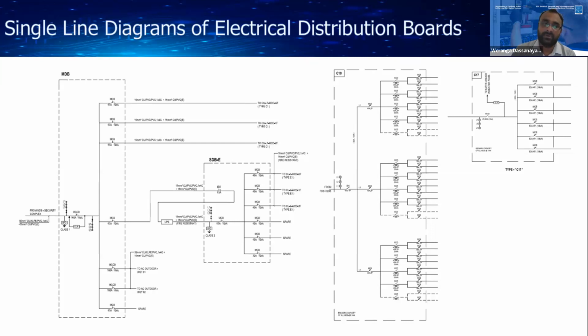So it is very important to understand the single line diagram when you are examining an electrical low voltage system, because all as-built drawings or design drawings of an electrical system are interpreted using this single line diagram. Here, main circuit breakers, ELR, surge protective devices, and main MCBs are all shown in this single line diagram, and where they are to be placed in the system is clearly indicated. So the next very important thing is you have to learn how to read a single line diagram.